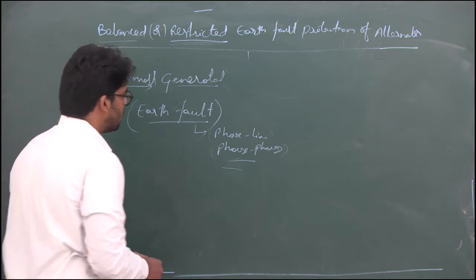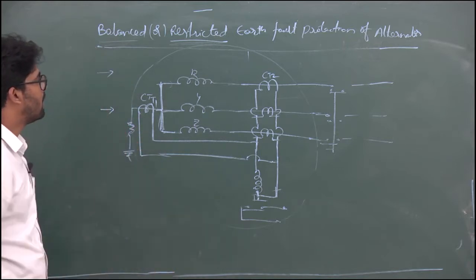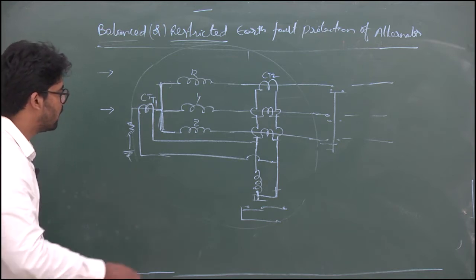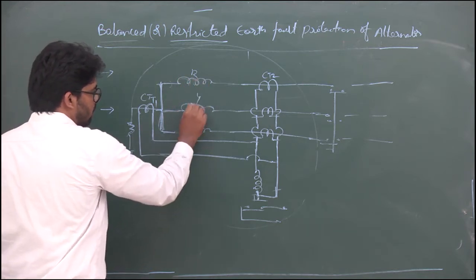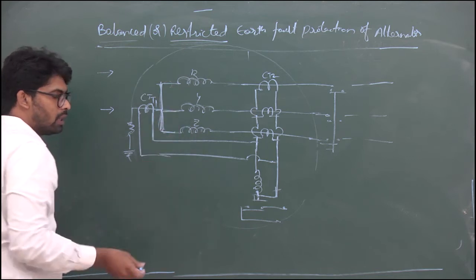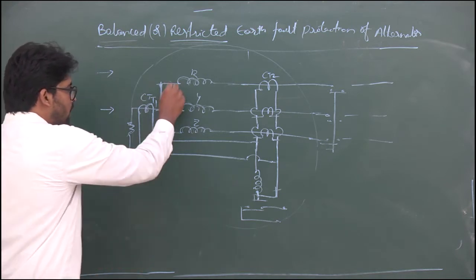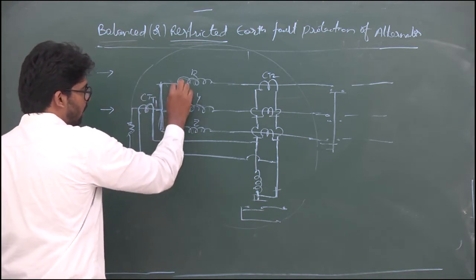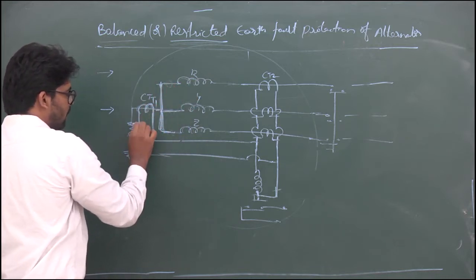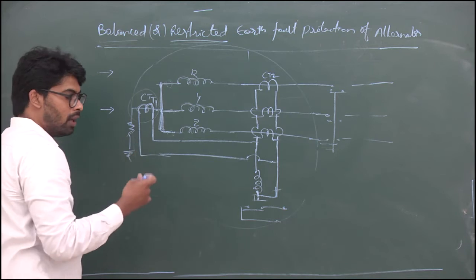The circuit configuration is given like this — this is the configuration of a balanced or restricted earth fault protection of an alternator. If you see carefully, these are the stator phases: this is the stator 3-phase, R phase, R/Y/B. Compared with differential protection and modified differential protection, we have individual CTs. Individual secondary CTs operate here, but the end terminals are connected together with one single CT, so the entire thing will be monitored by this CT only whenever a fault occurs.